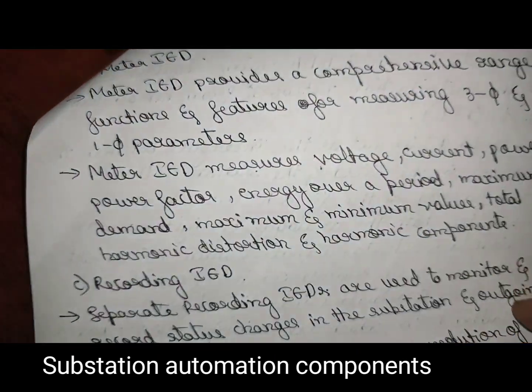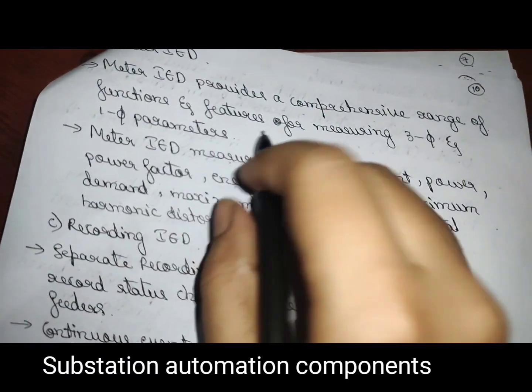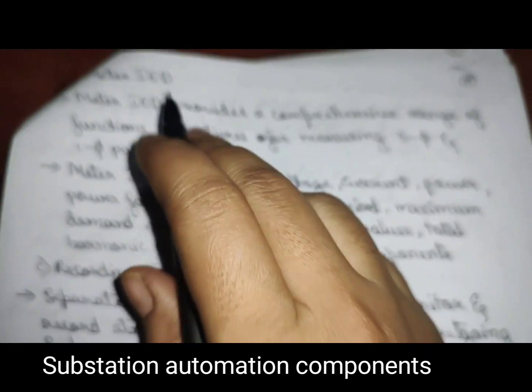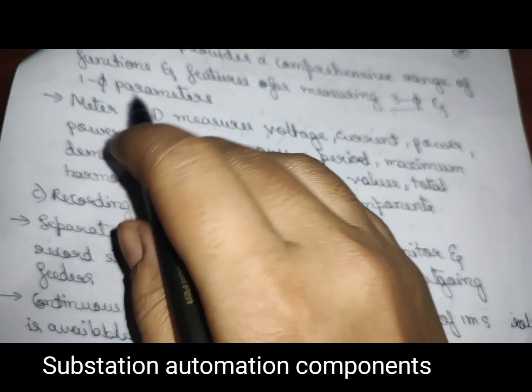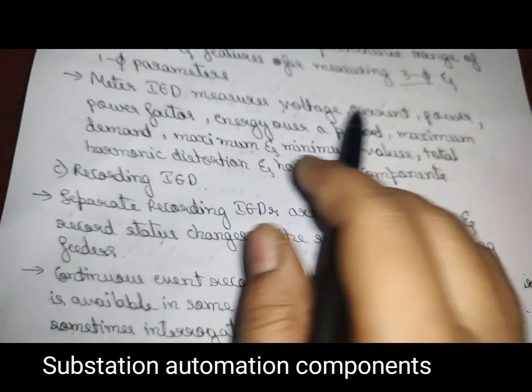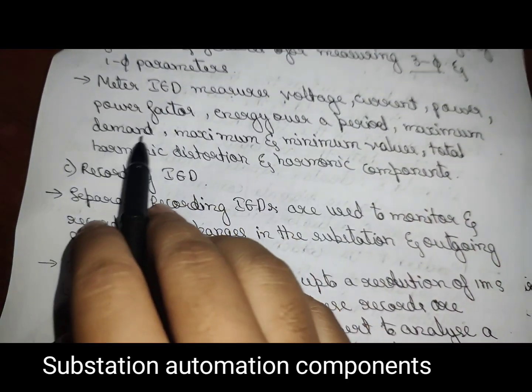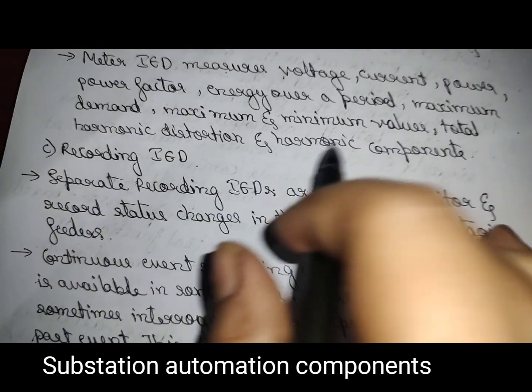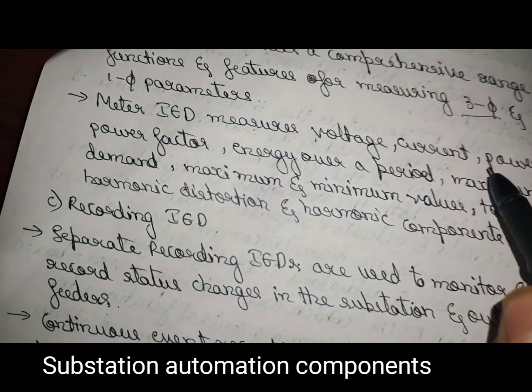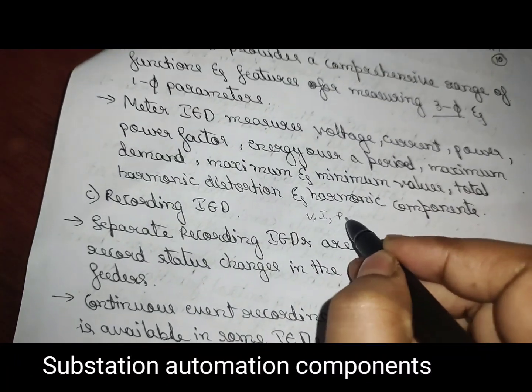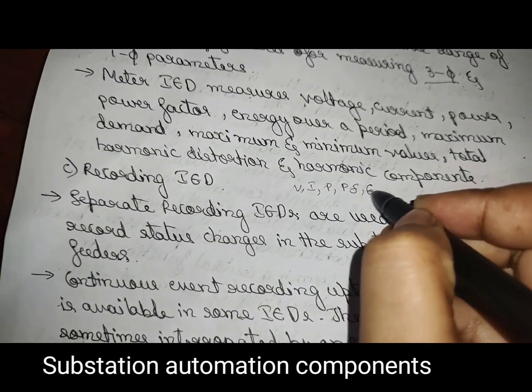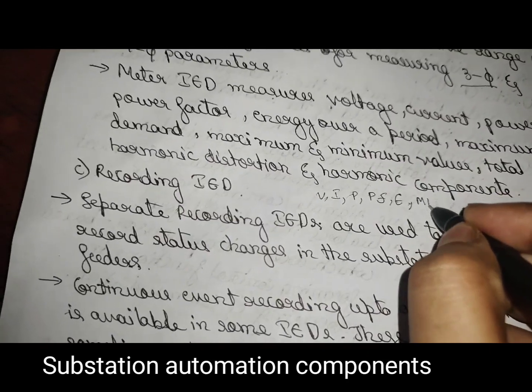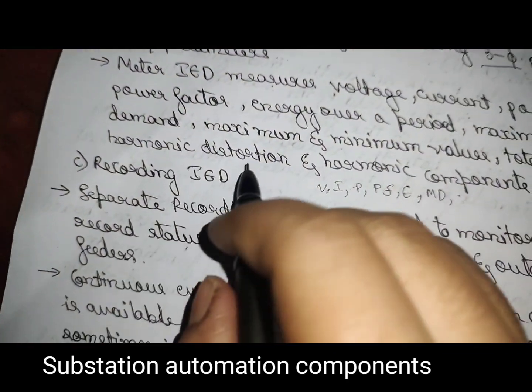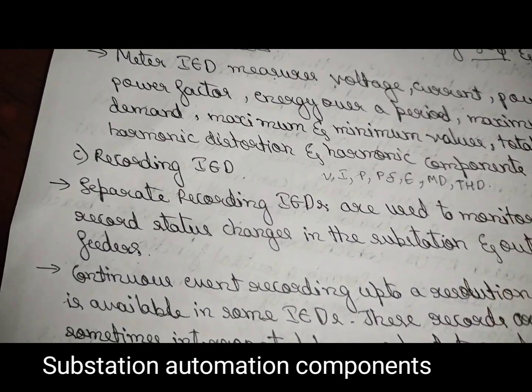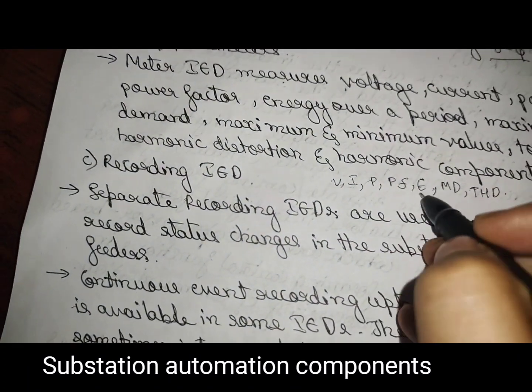Here, meter IED. In meter IED, it has a range of functions and features for measuring three-phase and single-phase parameters. Which measurements does the meter IED make? Meter IED measures voltage, current, power, power factor, energy over a period, maximum demand, maximum and minimum values, total harmonic distortion and harmonic components. So voltage, that is V, I, P, PF. And energy over a period, maximum demand MD, maximum and minimum values, total harmonic distortion THD. You remember this enough: voltage, current, power factor, energy and maximum demand.